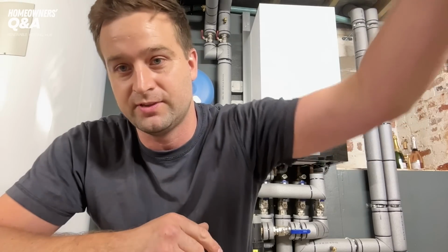So did you actually go and pull out and replace all of the pipework, or did you actually end up reusing what was there already? Yeah, well, interestingly, we talked about 4 times the flow of a condensing boiler. When the original heating system was put in, it was put in for probably DT11, so somewhere in between. So actually, a lot of the pipework was of good size, but I've ripped it out and started again because it was in the wrong place. I switched the heat source from one end of the house to the other, and also it was full of black sludge. So I'm not going to put that on, so I just started again.